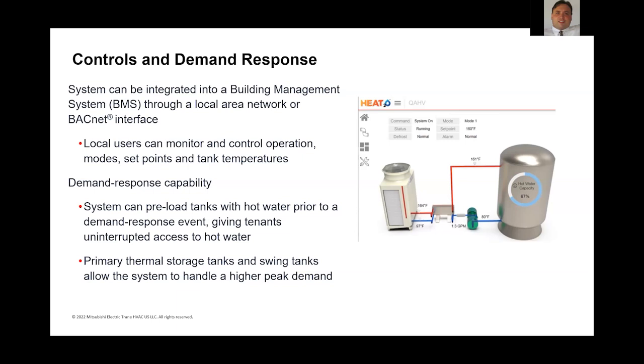So again, more commonly, this would be something like a time of day off-peak period, where you have advantageous demand rates, and you need to demand limit during a peak period. So you may have load up periods that the BMS system communicates to these heat pump supervisory panels, and you'll pre-charge your tanks maybe to hotter water temperatures than what you could achieve during those critical heating dominant periods, or colder ambient periods, I should say, in the winter months, where you have that higher heat output available, and pre-charge those tanks to higher temperatures to get you through those peak demand periods, say in the afternoon during the summer, if that made sense based on your specific utility structure.